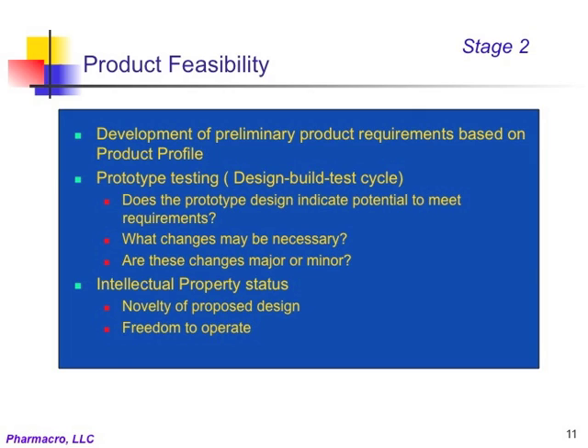Feasibility testing is then conducted by designing prototypes, building, and then testing them. Feasibility may involve a few iterations with design modifications to arrive at a version that has the highest likelihood of meeting the preliminary specifications. At this stage, it is normal to encounter specs that cannot be readily met without modifications. In that case, the specs are modified, and if any of these modified specs have implications with respect to the product profile, then the product profile is updated accordingly. Clearly, the important consideration is that the user needs will continue to be met by the updated product profile.